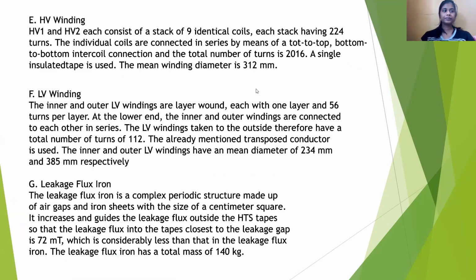HV winding. HV1 and HV2 each consist of a stack of 9 identical coils, each stack having 224 turns. The individual coils are connected in series by means of a top to top, bottom to bottom intercoil connection, and the total number of turns is 2016. A single insulated tape is used. The mean winding diameter is 312 mm.